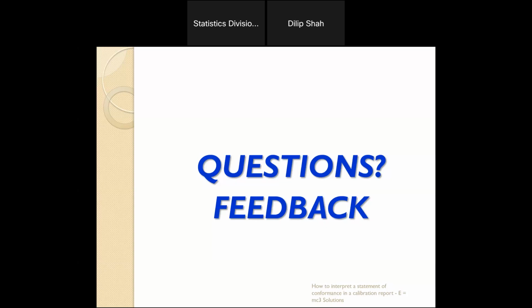Now, let's talk about measurement uncertainty. Measurement uncertainty in the GUM requirement, and in my slide I said you look at the ILAC P14 requirements for what a calibration supplier is going to give, but A2LA, one of the accrediting bodies, has a good guideline on it, and I call that the 5 R's and an E. They said these are the things you should consider: repeatability, reproducibility, but not the way the gauge R&R is done.